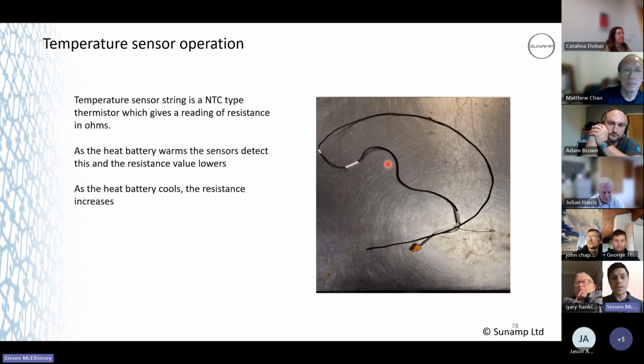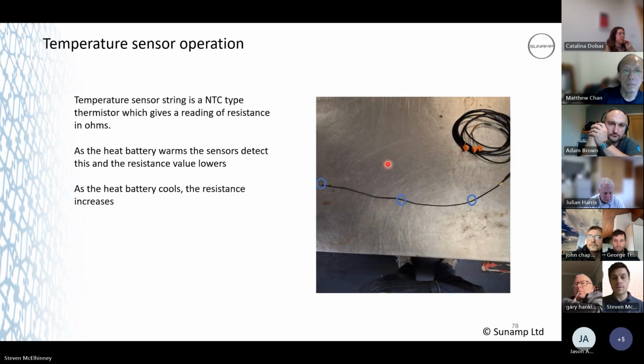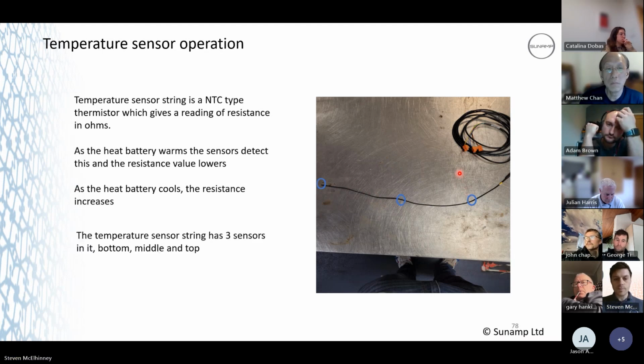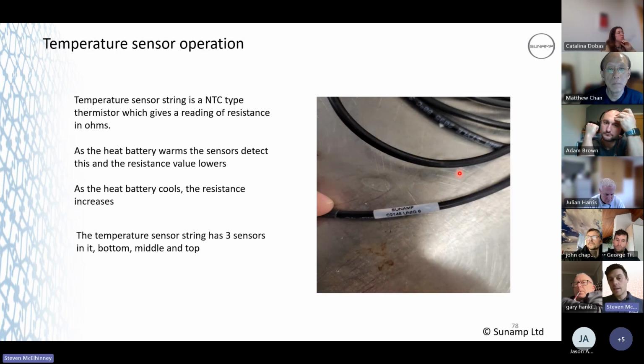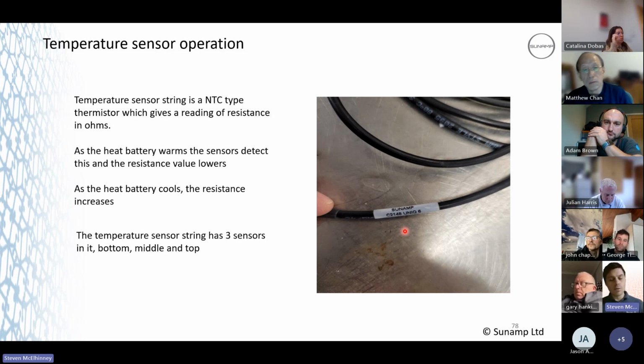So that's a temperature sensor. It's an NTC type. Again, you've got your bottom, your middle, and your top in there, and they are all marked. This is the old money. So now we've got Thermino 70, 150, 210, and 300. The third generation was a UniQ 3, 6, 9, and 12. I don't think they've changed the labeling on it.